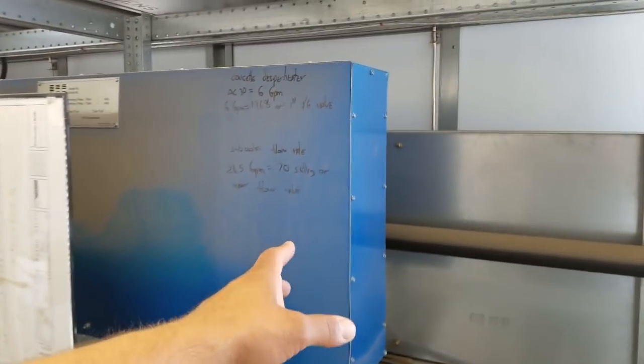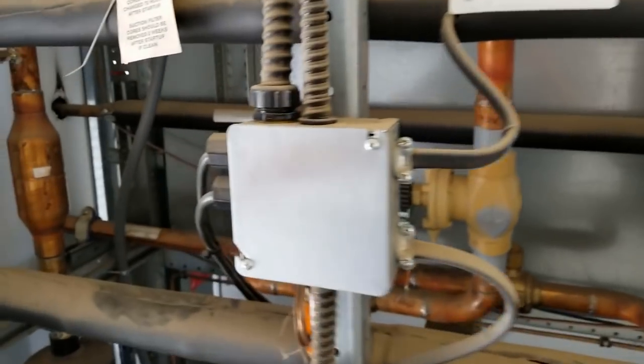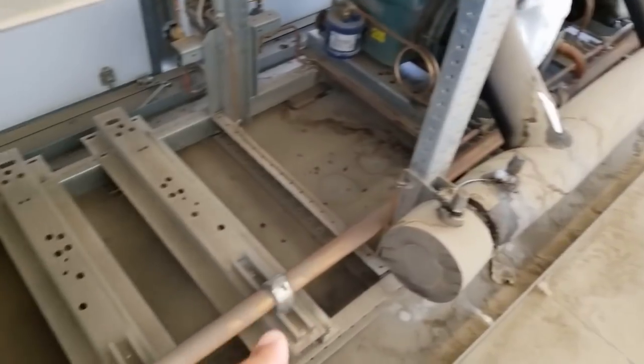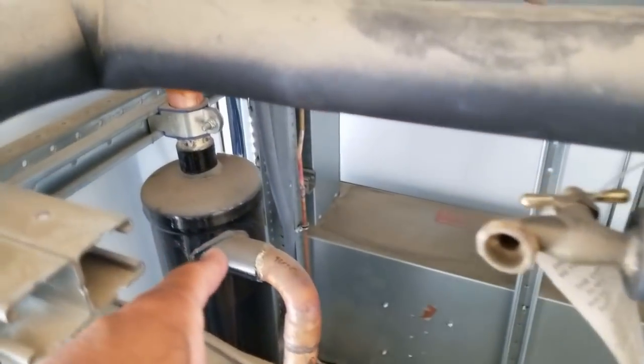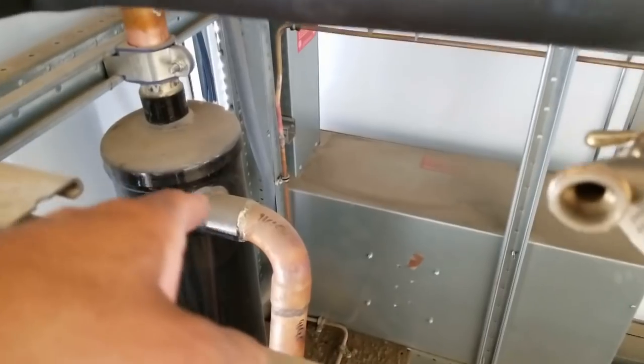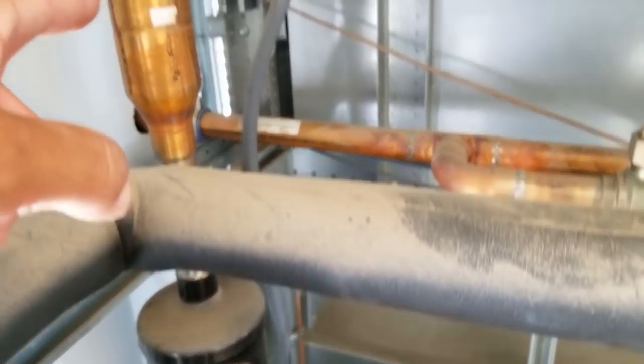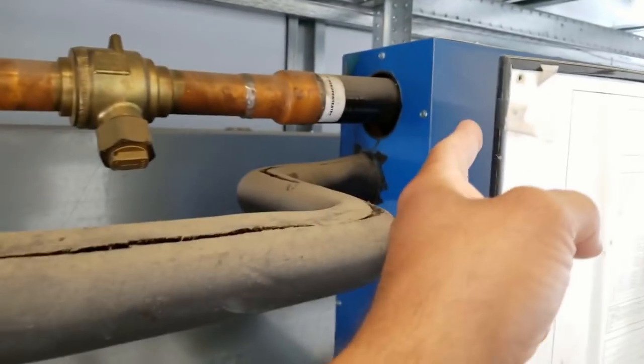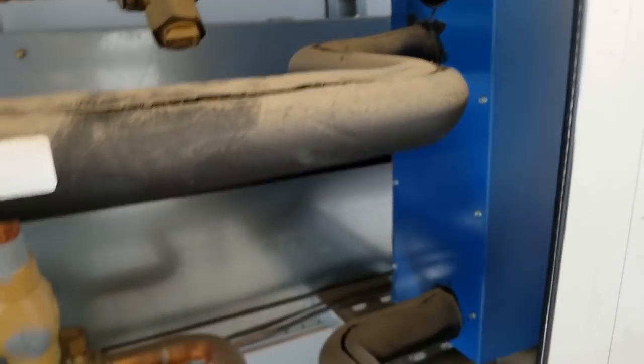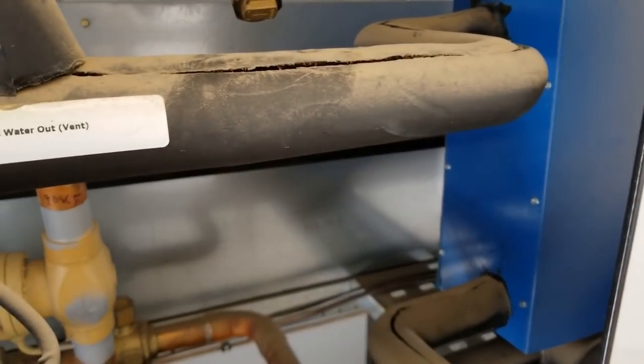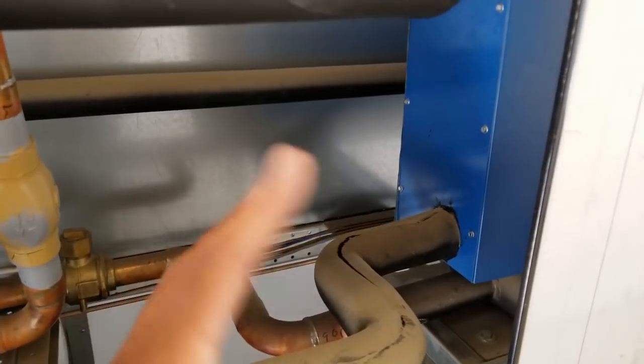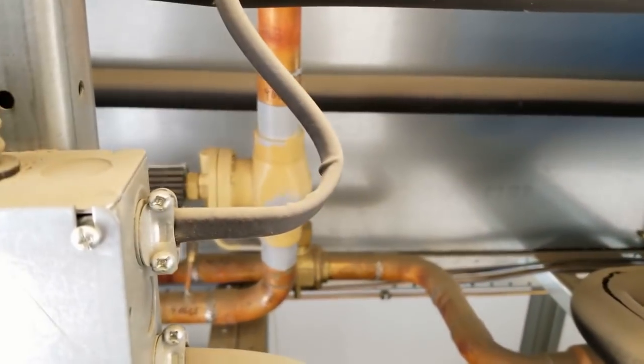And this is your heat reclaim tank right here. It's a little small guy. And it works off the discharge line. The discharge line comes off of the compressors, like here it is right here. Your discharge line goes into your separator, and then it comes off the top of your separator and goes into your heat reclaim tank. Then you have cold water coming in, hot water going out, and it's just a little bit more efficient that way. Might as well heat up water with this discharge.